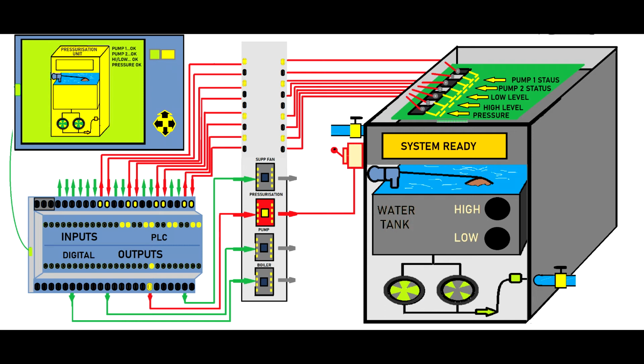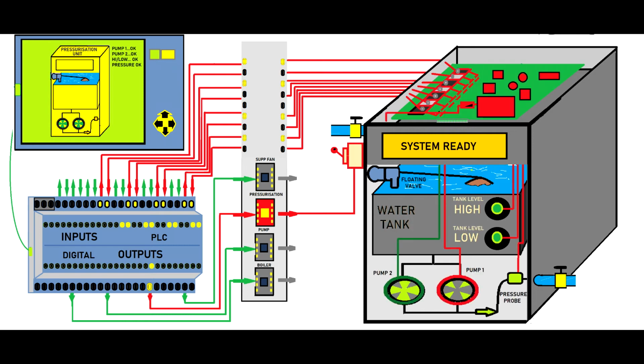So you've seen that the programmable logic control collects data from the PCB and returns the data according to the system health. As I told you, the motors, as you'll see, the green and the red wire go straight to this printed circuit board, and also the high and low level switch and the pressure transducer go onto the printed circuit board.